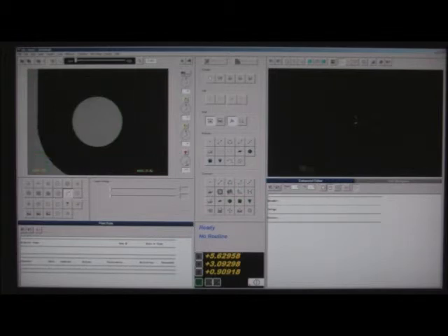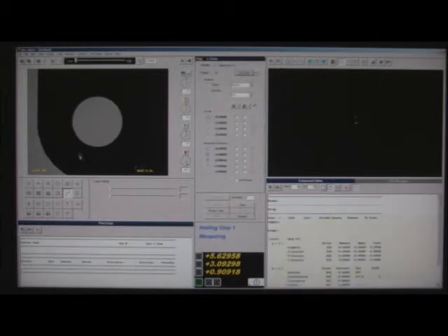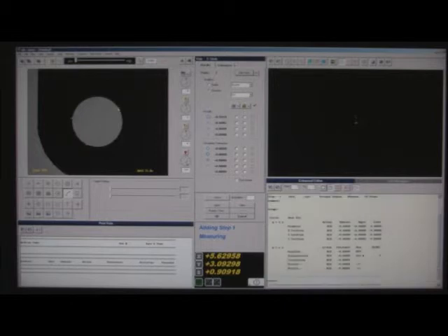And what this target lets us do, if I select measure a circle in the center of the screen, is this: if we had an edge that was so rough that I can't physically measure it with any of the automatic tools, but in a program I still want it to initiate and move to the position to tell the operator where to measure on a part. The operator would just physically move the cursor to wherever he wants to take points.